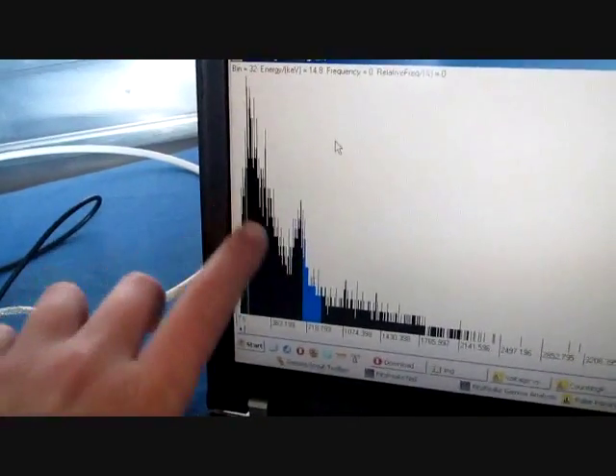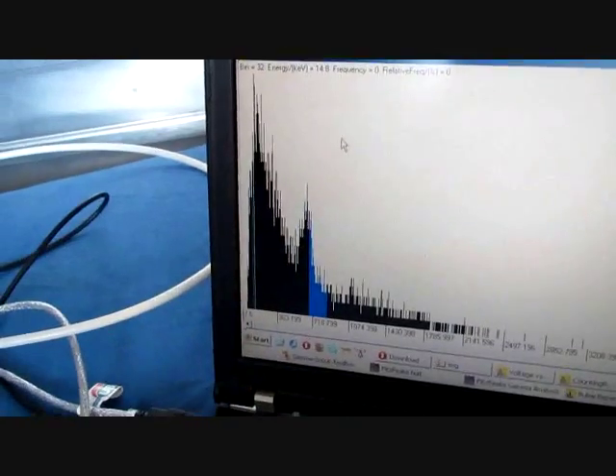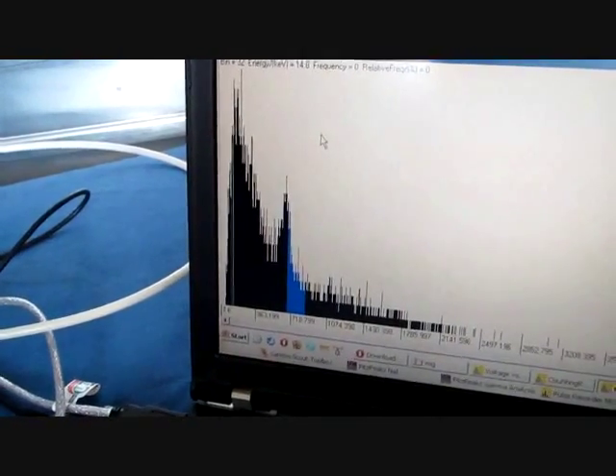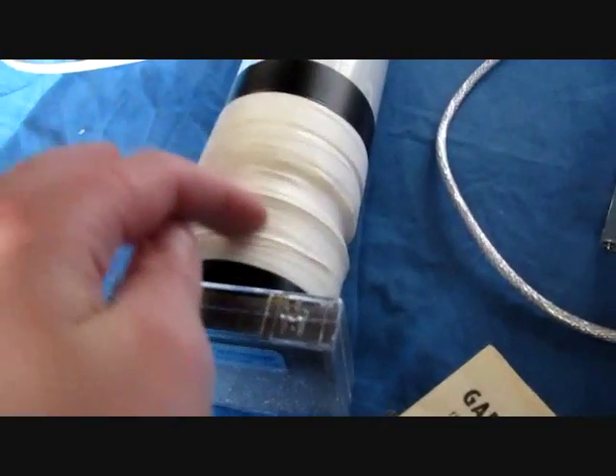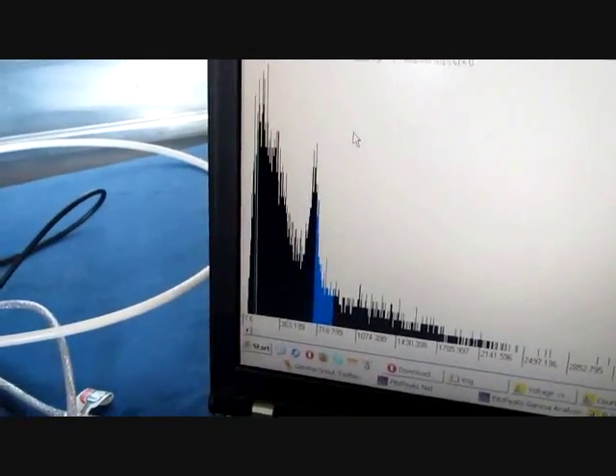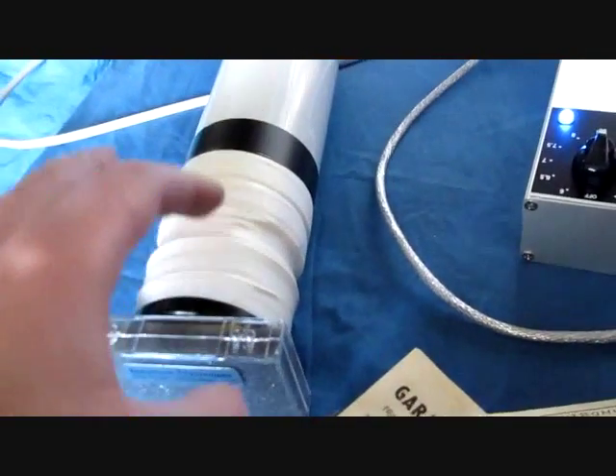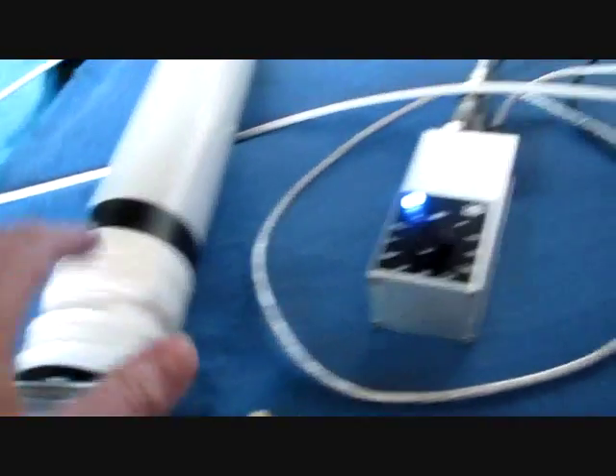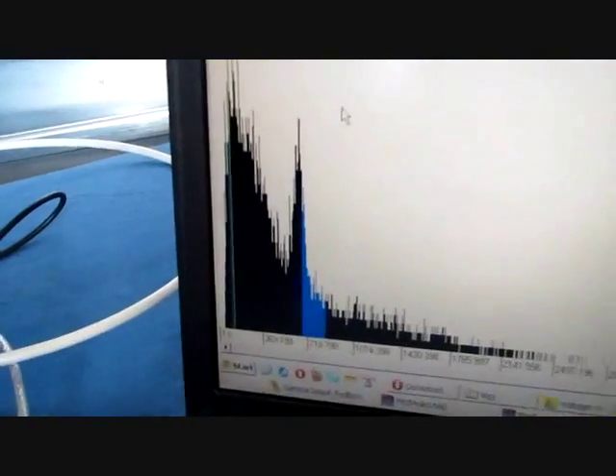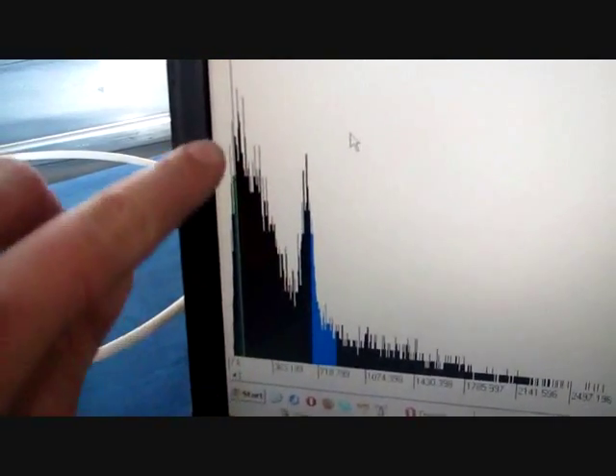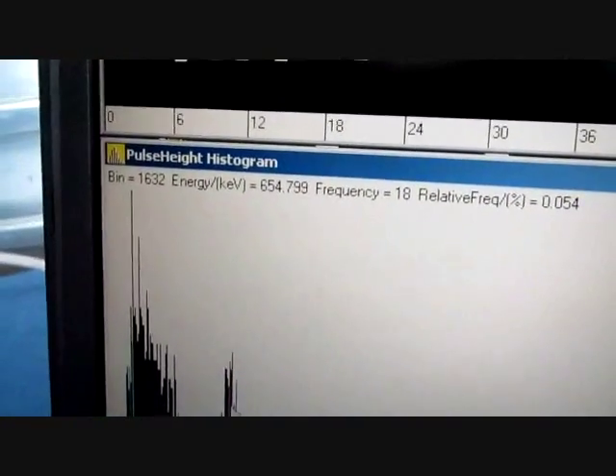This would be the Compton continuum, because the actual photo peak happens because of the photo effect, when the gamma quantum deposits the whole energy within the detector, and the maximum energy transmission happens, and that results within the photo peak. But it could also be that the gamma quantum striking the detector only transmits part of the energy and does a so-called Compton scattering, and thus will be the Compton continuum in front of the actual photo peak. I also previously did some rough energy calibration, so it shows up as 654 keV.